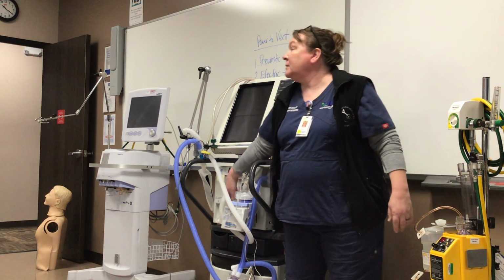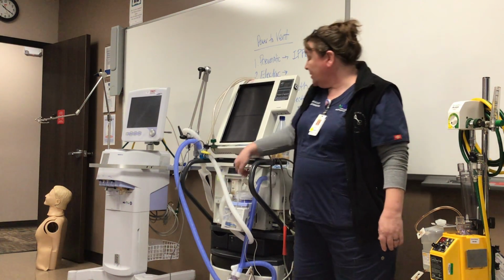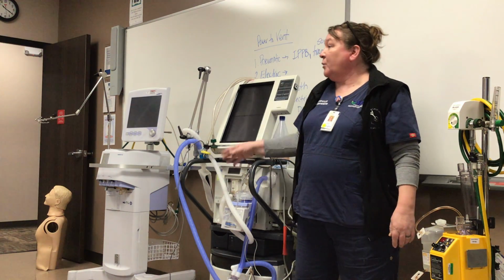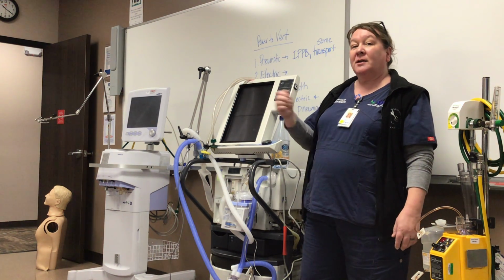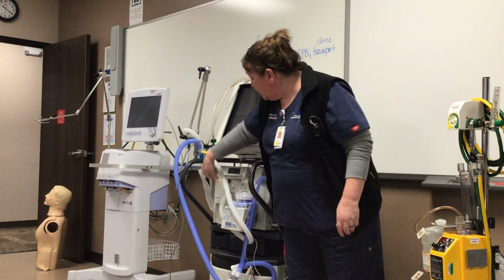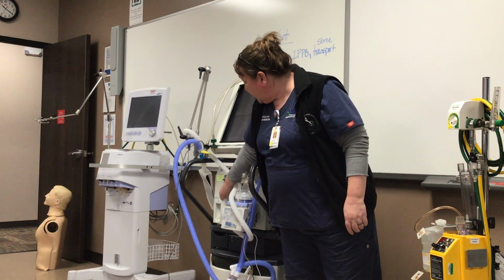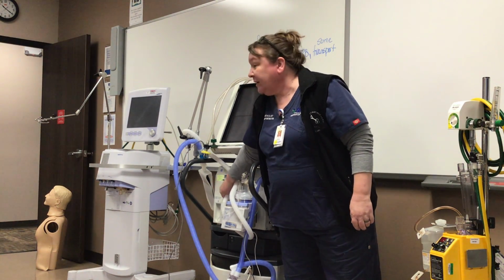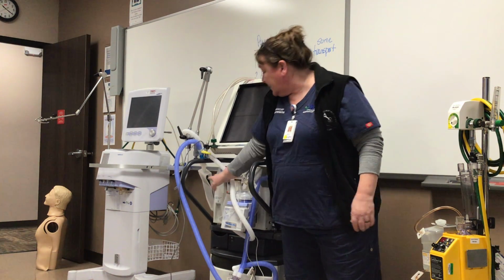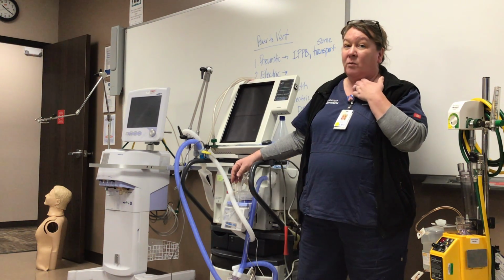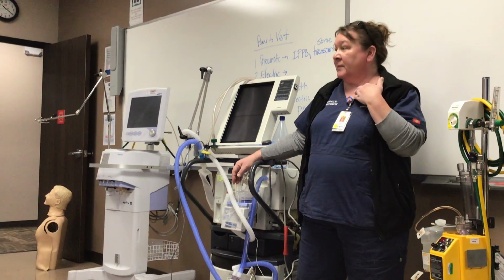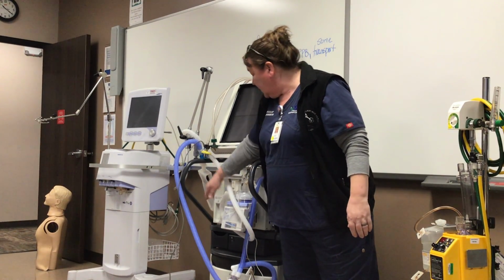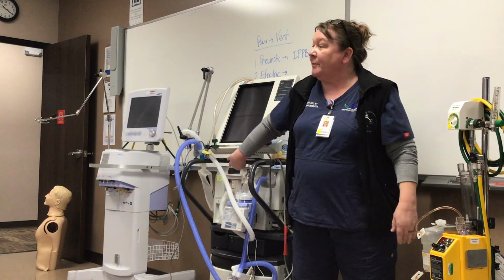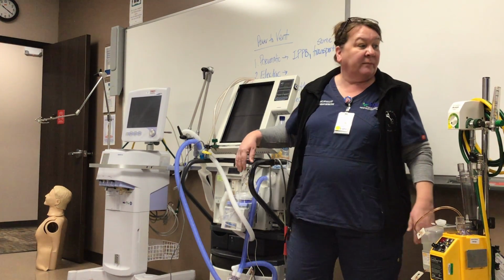So, is that per patient too? Yes, this filter is one per patient. So remember, that's going to be one of the things you take on and take off, because you also need to know, which you'll learn this, that if I flip up my little valve here and take it off, and then I put it back in and I don't flip the valve down, the vent won't work because it's not locked into place. But yes, that's one per patient. So the exhalation valve in the PB, we can't do anything with it, it's internal.